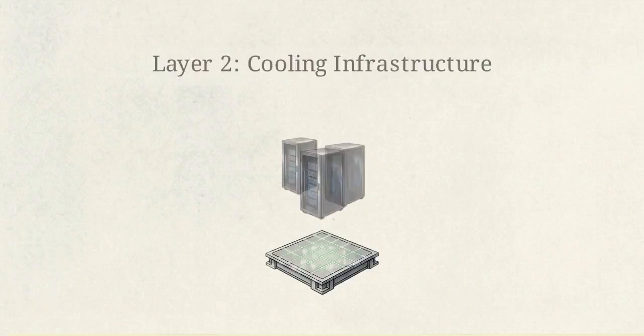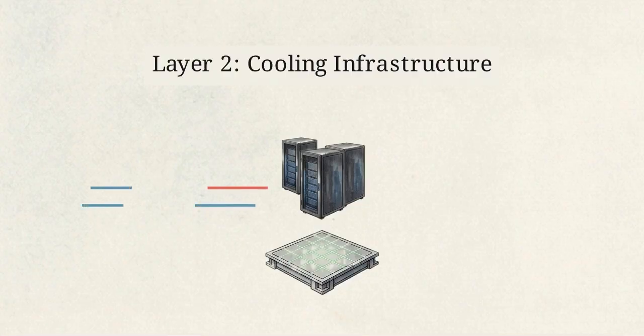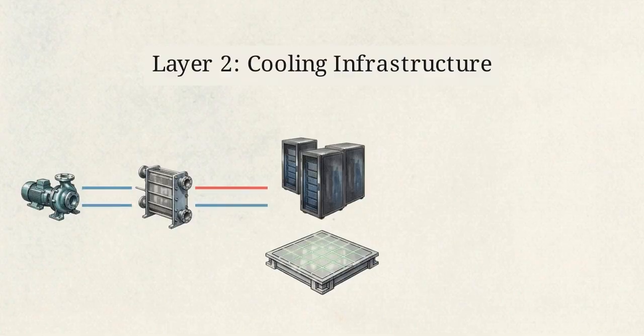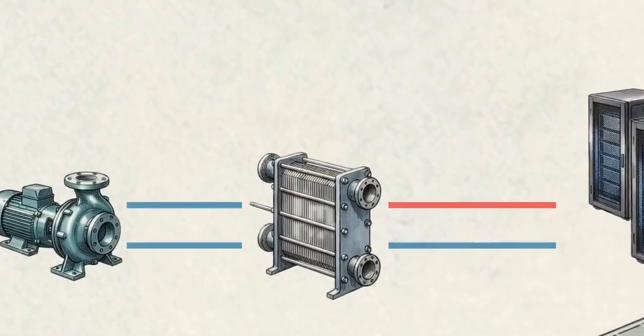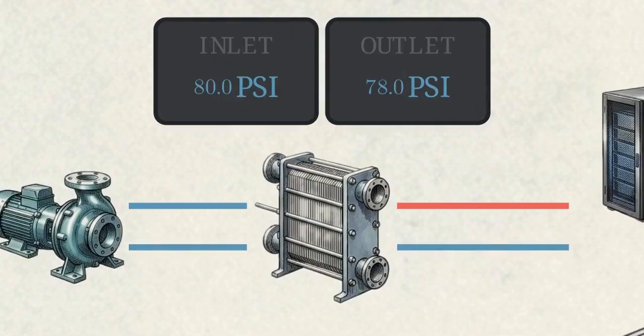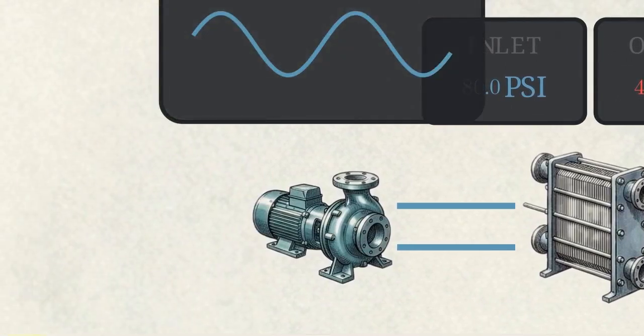Moving outward from the data hall, the architecture extends into the mechanical rooms. Layer 2 is the cooling infrastructure. This is the network of chilled water lines and direct-to-chip liquid cooling loops that absorb and transport the heat away from the servers. Look at the pressure readings across this heat exchanger. Comparing the input pressure to the output pressure is the most reliable way to diagnose internal scaling, fouling, or blockages deep inside the plumbing. Measuring the suction and discharge pressure directly at the pumps reveals hydraulic instability. Erratic fluctuations indicate trapped air or a degrading impeller that will soon fail under load.